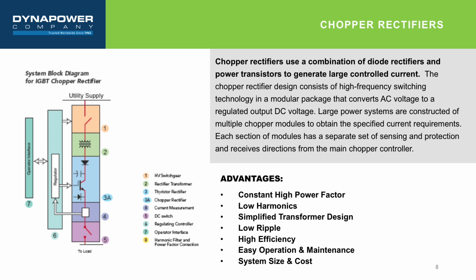The chopper rectifier design consists of high-frequency switching technology in a modular package that converts AC voltage to a regulated output DC voltage. Large power systems are constructed of multiple chopper modules to obtain the specified current requirements. Each section of modules has a separate set of sensing and protection and is controlled by the main chopper control. The operating advantages that we will examine today are power factor, harmonics, ripple, transformer design, system response, efficiency, and system size and cost. We will examine each one at a time.